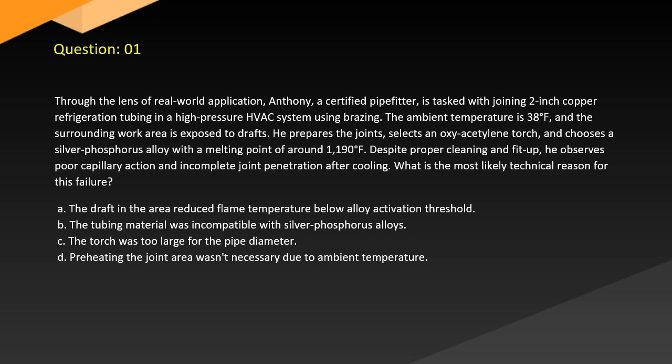Question 1. Through the lens of real-world application, Anthony, a certified pipefitter, is tasked with joining 2-inch copper refrigeration tubing in a high-pressure HVAC system using brazing. The ambient temperature is 38 degrees and the surrounding work area is exposed to drafts. He prepares the joints, selects an oxyacetylene torch and chooses silver phosphorus alloy with melting point of around 1,190 degrees.